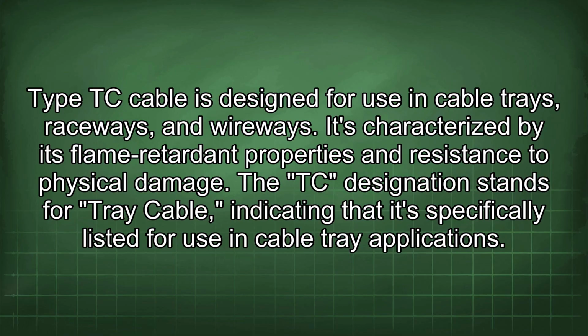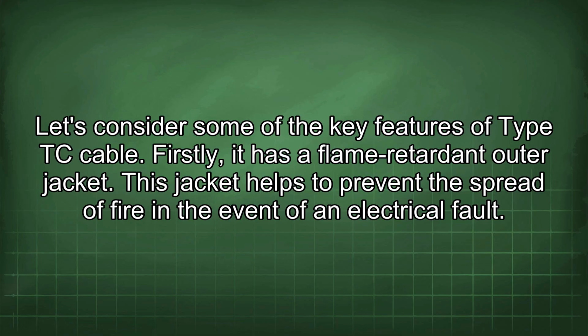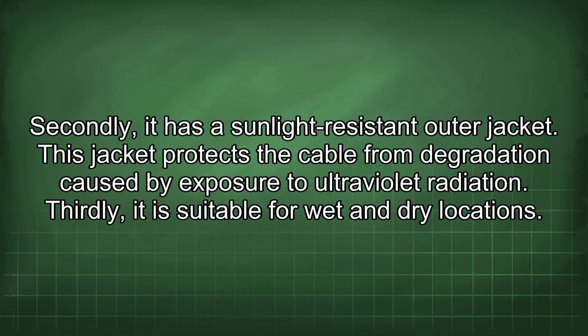The TC designation stands for tray cable, indicating that it's specifically listed for use in cable tray applications. Let's consider some of the key features of Type TC cable. Firstly, it has a flame retardant outer jacket. This jacket helps to prevent the spread of fire in the event of an electrical fault. Secondly, it has a sunlight-resistant outer jacket. This jacket protects the cable from degradation caused by exposure to ultraviolet radiation.